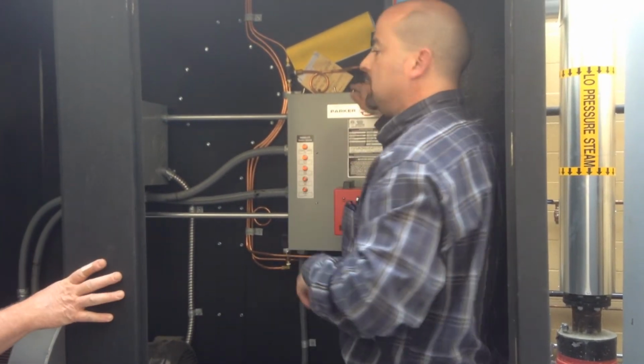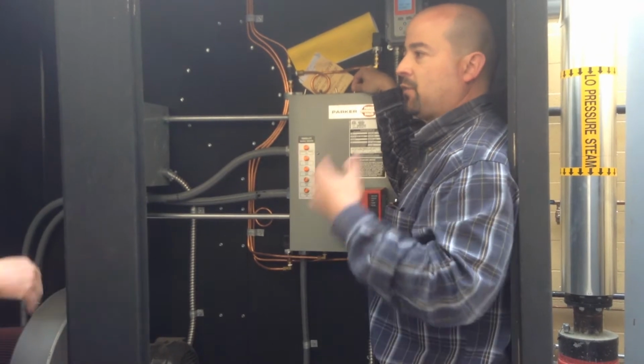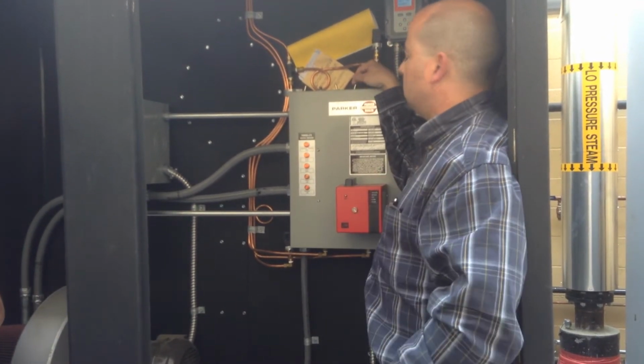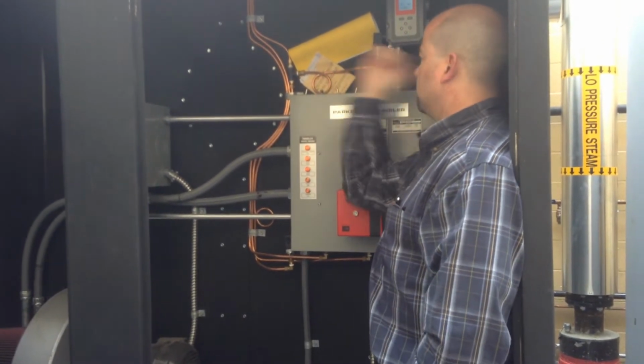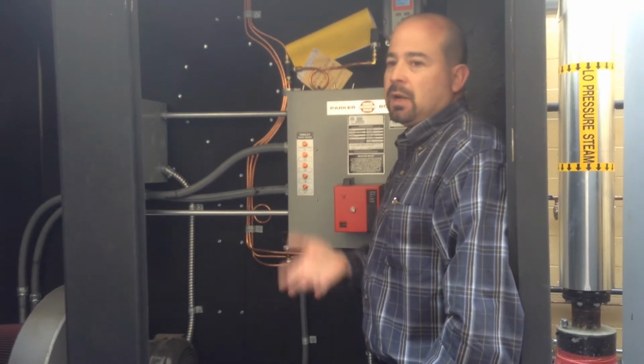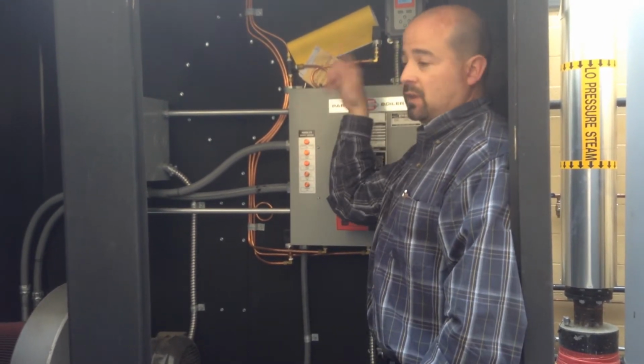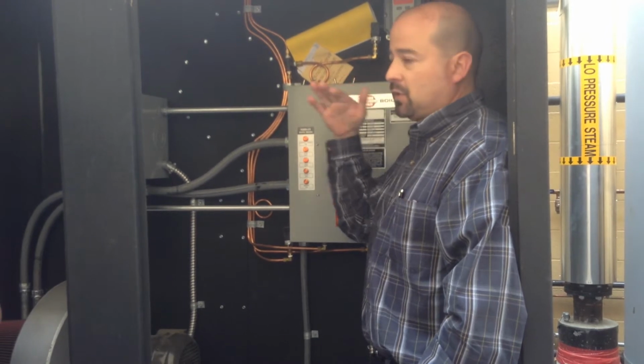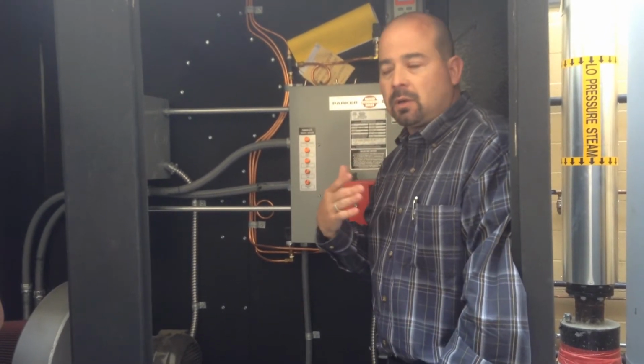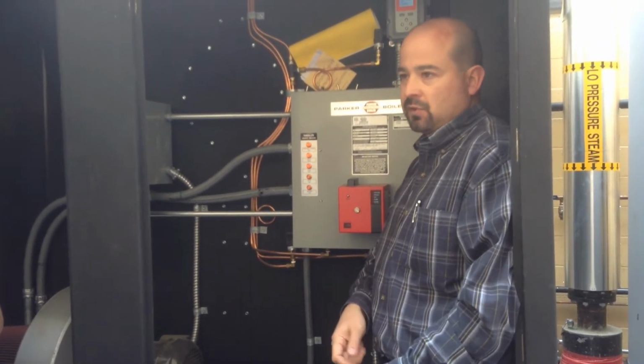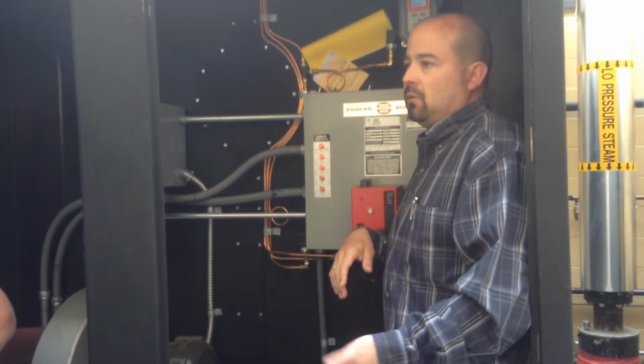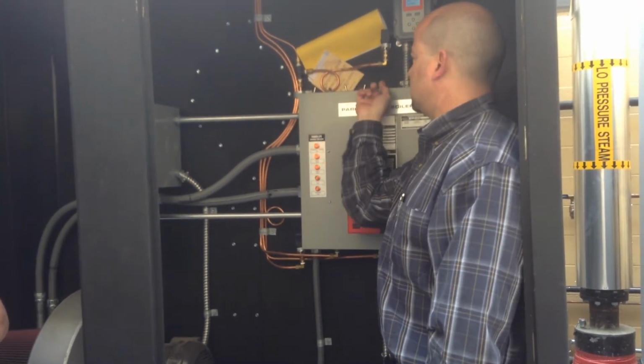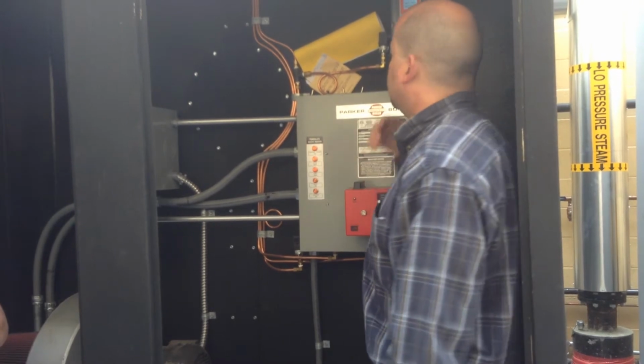Okay, so this switch here, you guys really should never touch. It's for us, for tuning. It's a low fire hold switch. So when it's to the right, it allows it to go to full modulation into high fire. When it's to the left, it tells it to go into low fire. Because when we do our combustion tuning, we have to tune it in low first, and then we tune it in high. So we have to force it to low. So this is really just for us.